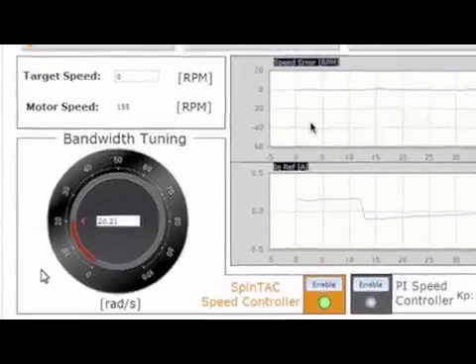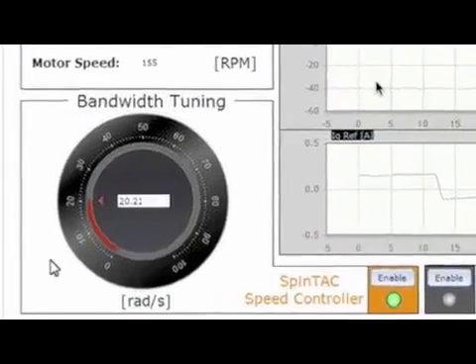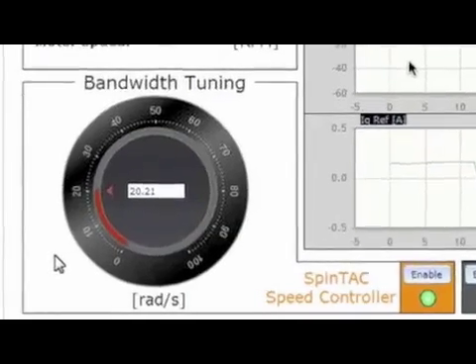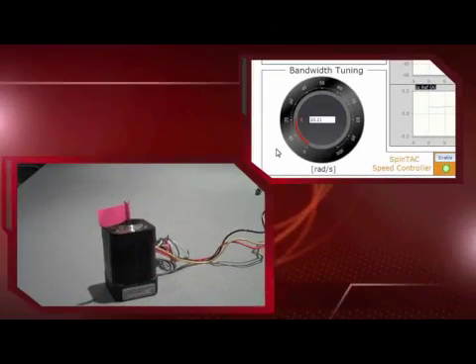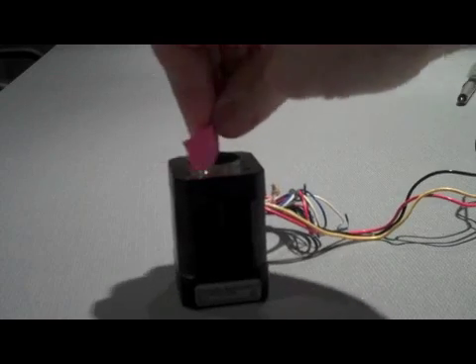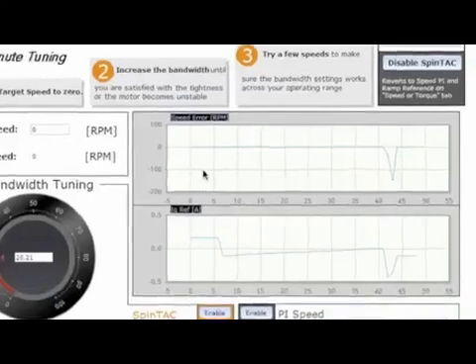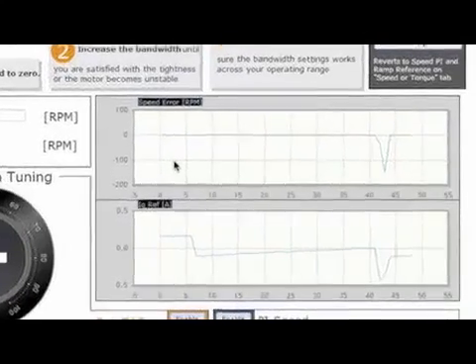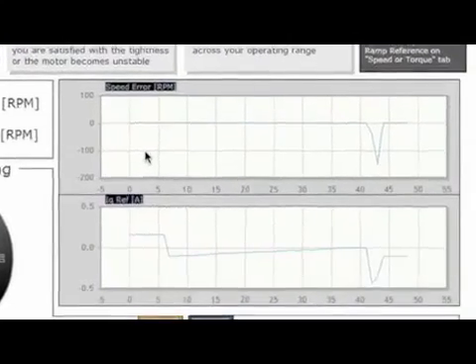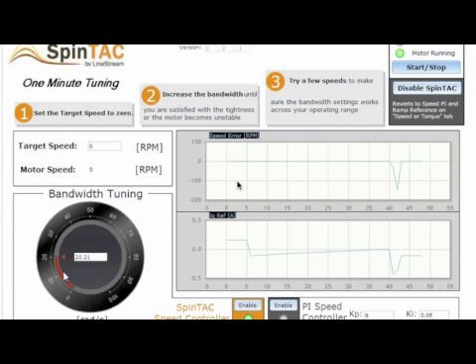A single parameter, called bandwidth, is used to tune the controller. The motor speed is set to zero, and we'll start with a bandwidth of 20. At this bandwidth, it's very easy to rotate the motor shaft. The GUI displays two graphs: the speed error and the IQ reference. The speed error tells us how far the motor is deviating from zero speed as we introduce manual disturbance by rotating the shaft. The IQ reference shows how strongly the controller is compensating for these disturbances.